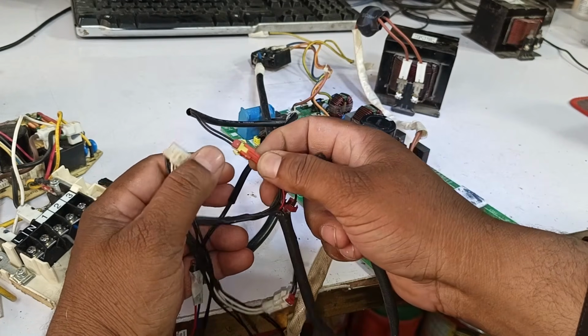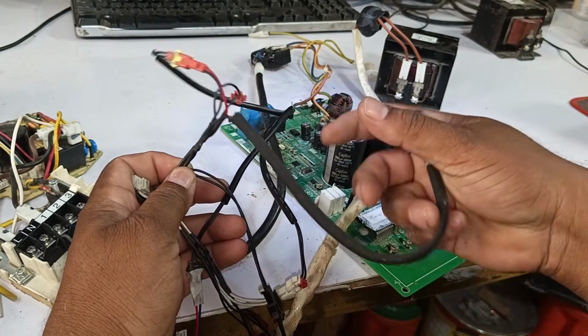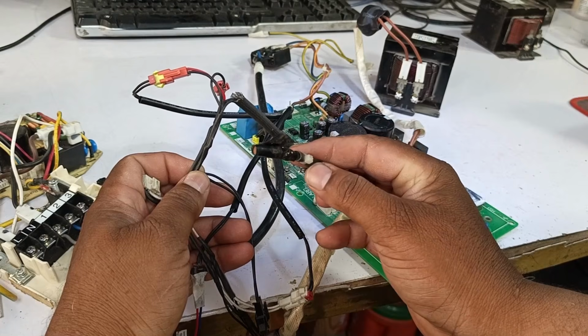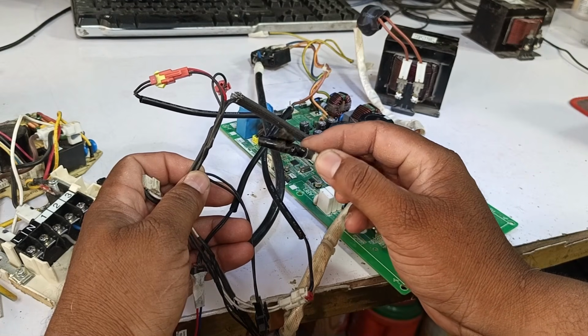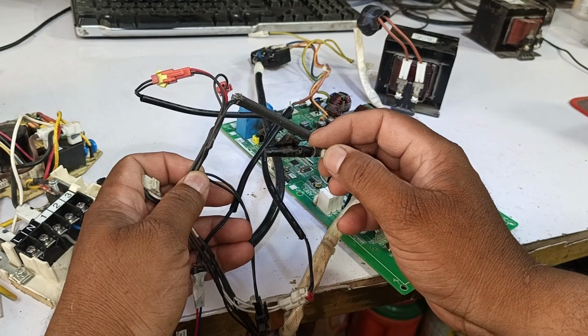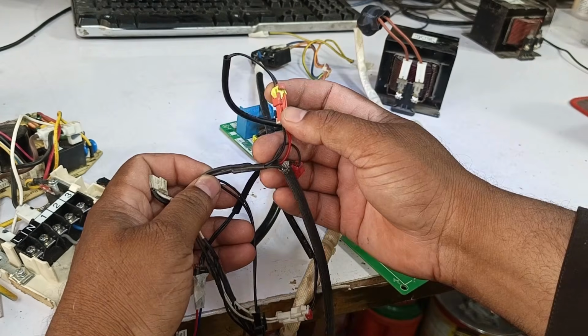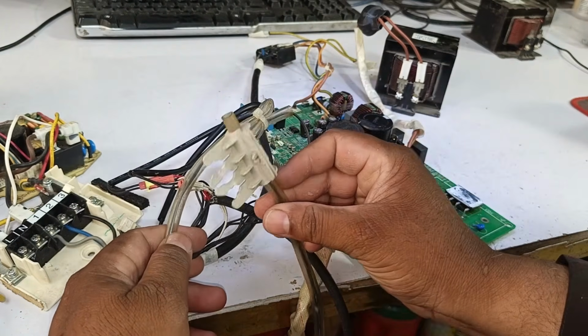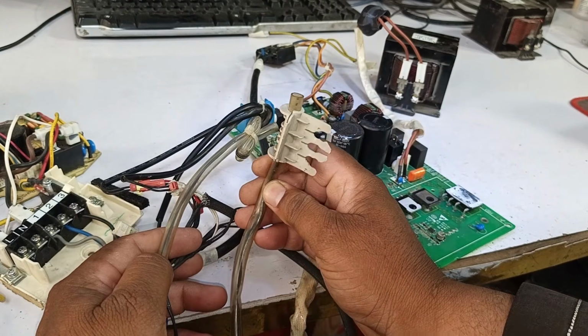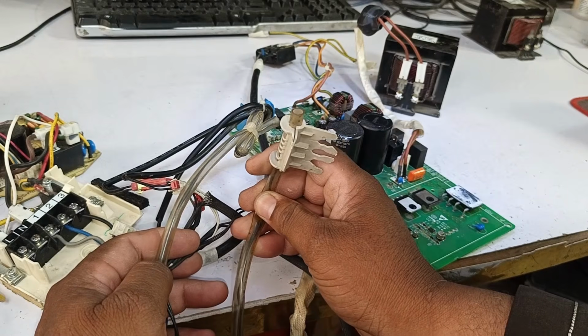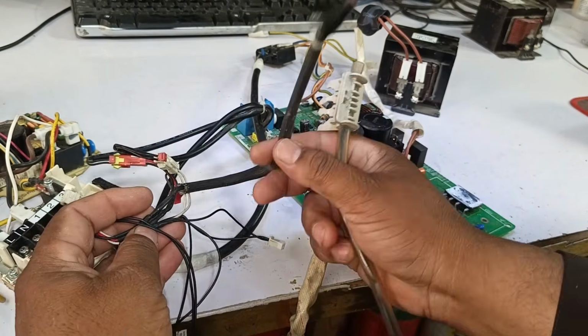So this sensor attaches to the compressor's discharge pipe. It means that its value at 25 degrees is approximately 50 kiloohms. So I have attached it to this. The white sensor is for the outdoor temperature. The sensor I have has this attached to it. Now, this is where the mistake happened. So I will show you.